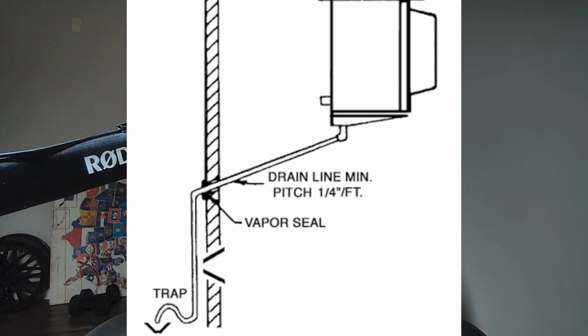On the commercial side, we've seen evaporator coils where the drain pans would be leaking, full of water. A telltale sign is when you see the bottom side sweating, or it tends to ice up, because the water has nowhere to go.